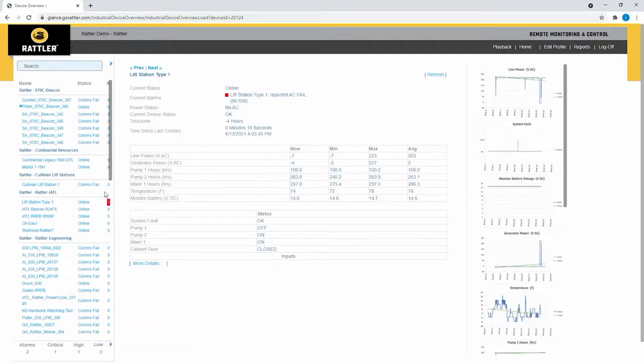Now you can see on the list on the left-hand side that the lift station is number 1 on the list. It's got an alarm. You can look at the alarms this way. You can see the lift station type 1 has reported AC fail. You can see that alarm over here. And so you can immediately see that this requires attention. It doesn't need you to call the lift station maintenance company. It needs you to call the power company because there's been an AC fail. But as I said, it was a short duration alarm which went away.